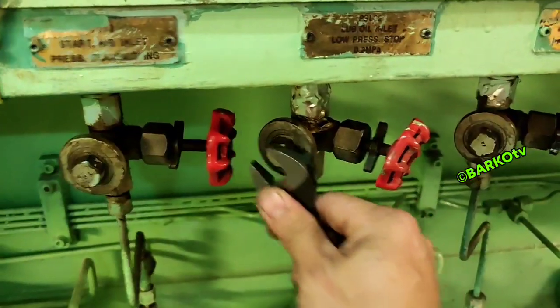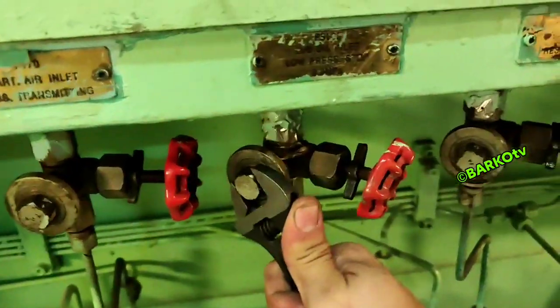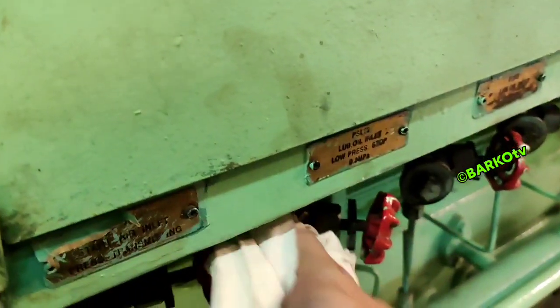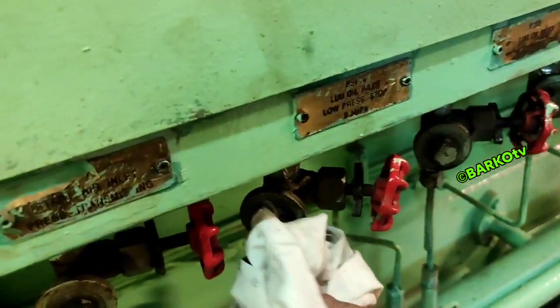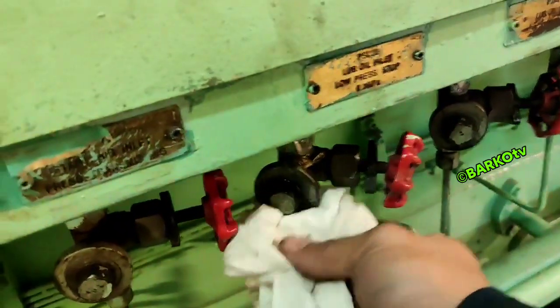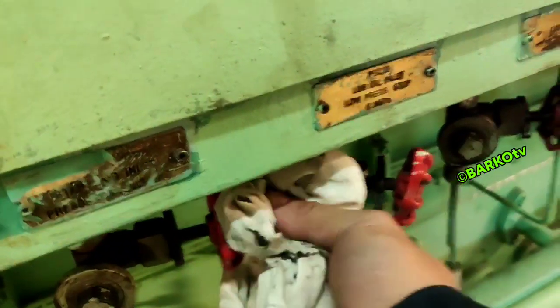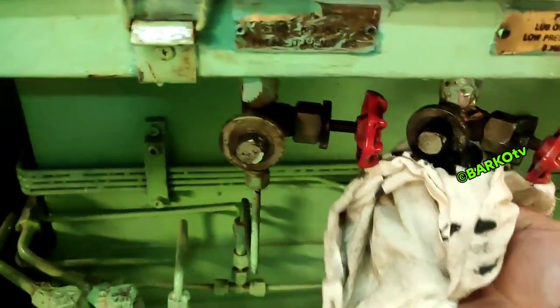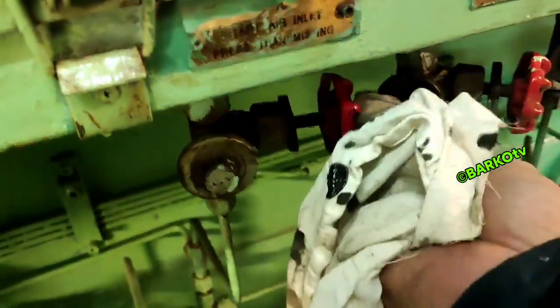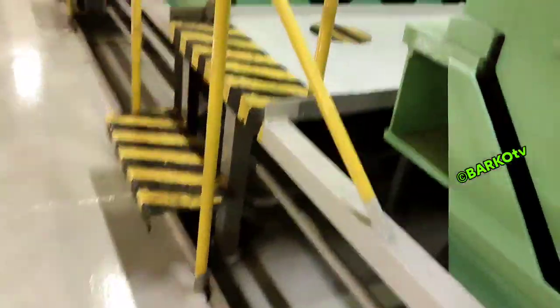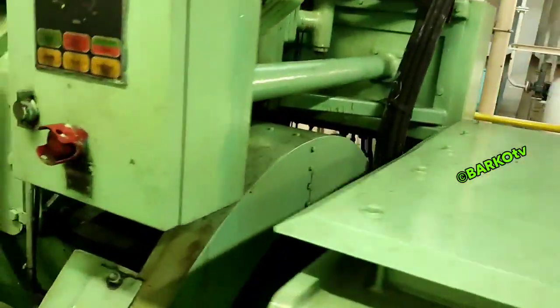Close this three-way valve and then open this vent. After opening this vent, the low pressure shutdown pressure switch must be activated. And then the generator activates shutting down with this low pressure switch. Okay. Then for that we already simulated the lube oil shutdown.